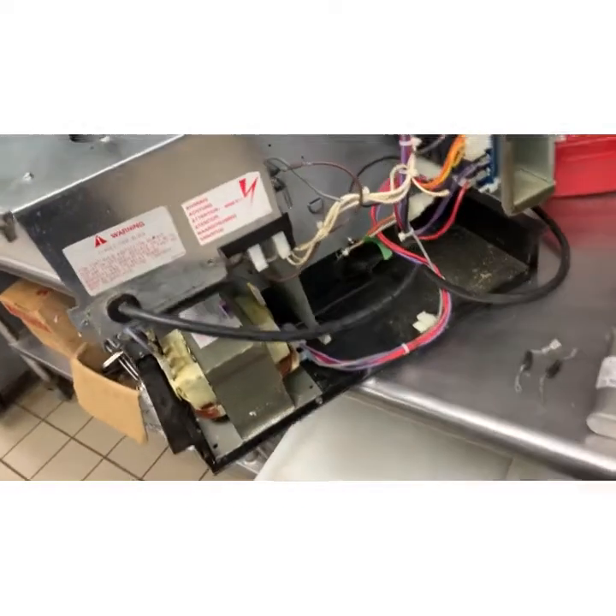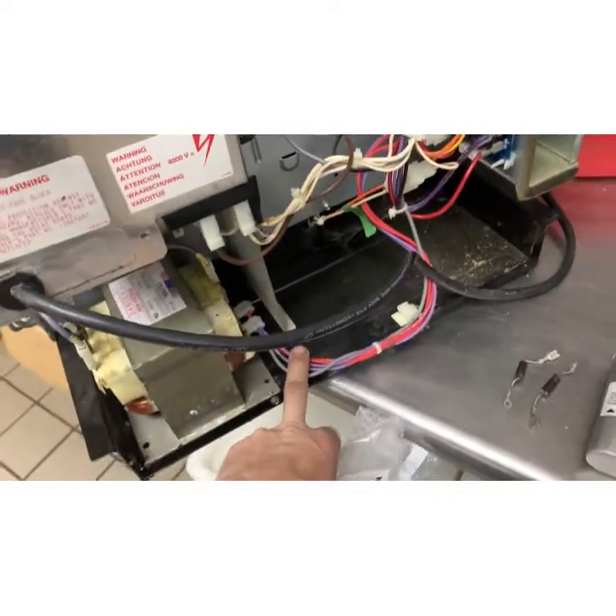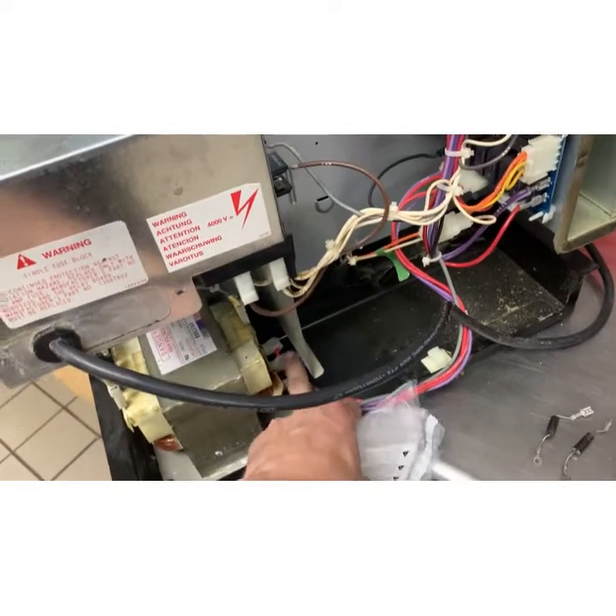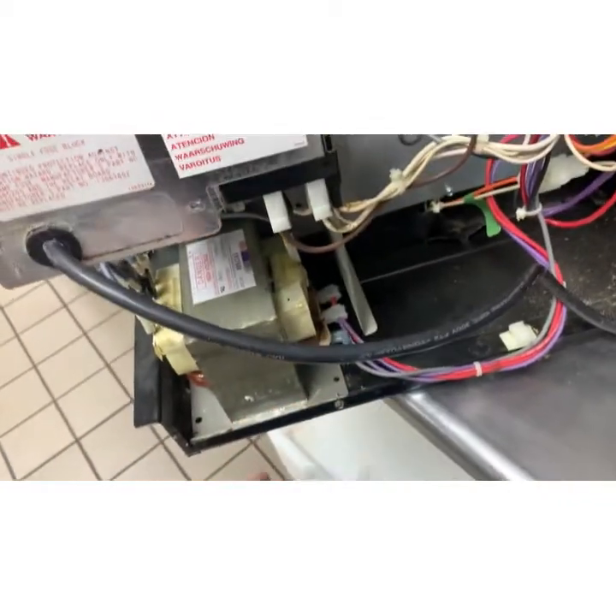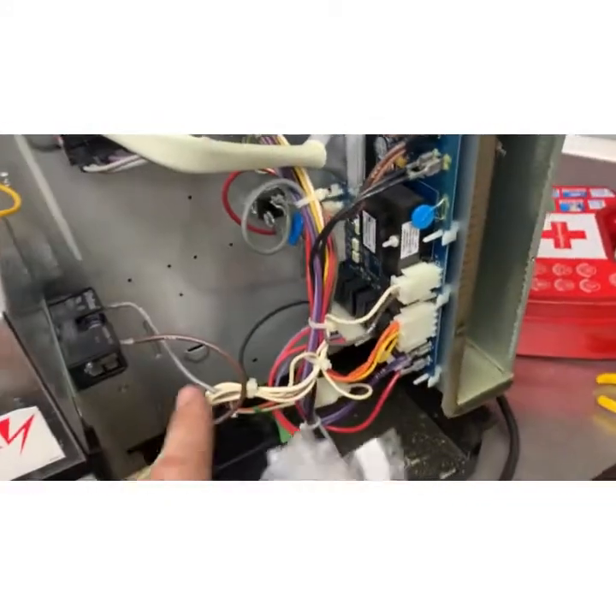Everything was good right into the transformer. When I disconnected the 208 and the neutral, took my meter to it, asked it to cook, I got 208. So systemically, electronically, the relays, the boards, catches, everything's working properly.